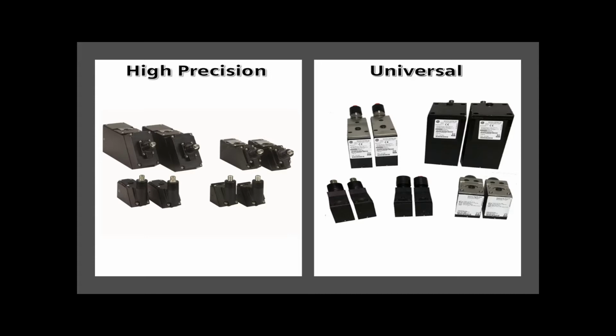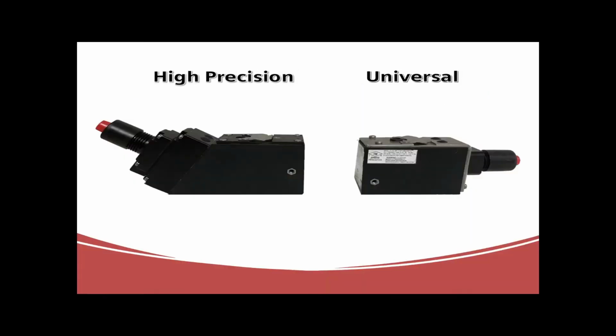Every sensor is designated by a letter-number combination. The letter represents the physical size of the sensor block. As you can see, high-precision sensors come in sizes from A through D, while universal sensors come in A through E sizes. While high precision and universals share sizes, they are really quite different. For comparison, here is both a C2 high precision sensor and a C2 universal sensor. Again, the C represents the physical block size, and the 2 represents its frequency range.